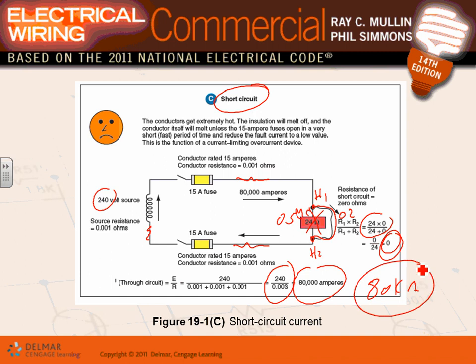80,000 amp, is that what we did? 80,000 amp. Gentlemen, and ladies, you are looking at a short circuit condition. Can you guys see what a short circuit condition is? That's your semi going at 110 miles an hour down Interstate 94 and hitting a brick wall. That 80,000 amp will do two things: shake and bake. It will shake your equipment, and it will bake it. Now imagine shaking a panel like this. What happened to the bolts? It's going to loosen everything. It's getting off the wall. And imagine you being standing right in front of this piece of equipment when that happens.